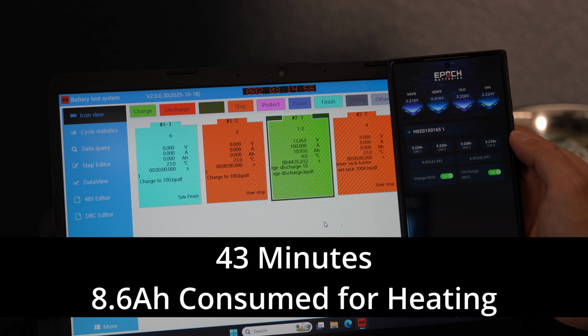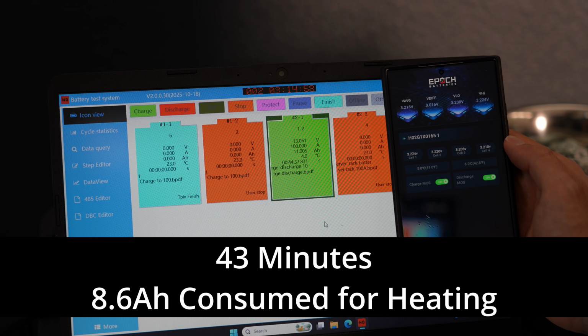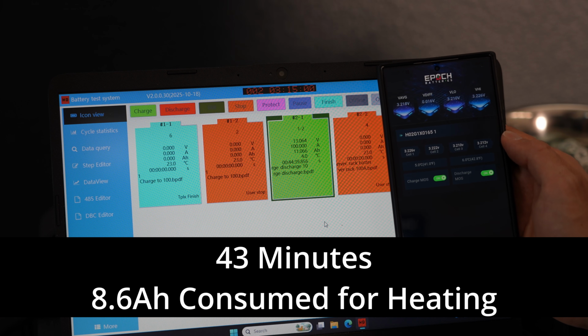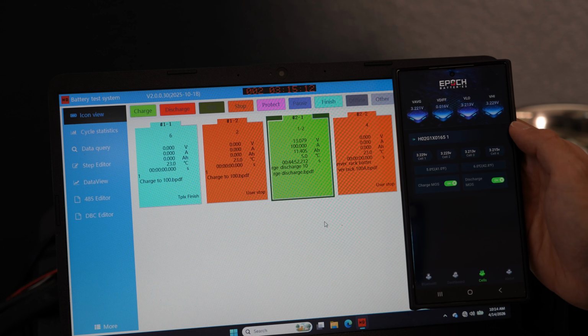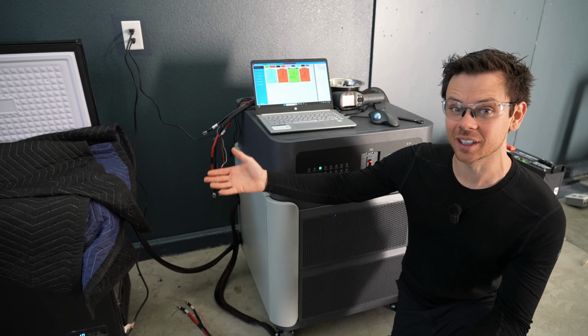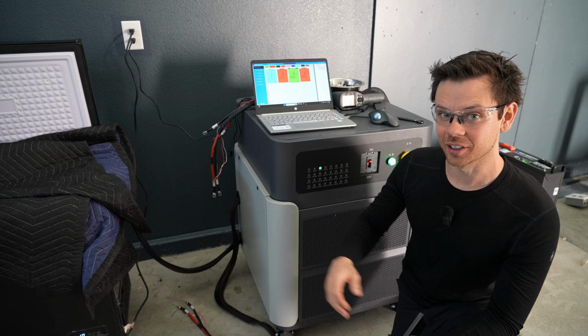So it finally started charging with 100 amps at 43 minutes, and we're at 5 and 6 degrees Celsius for the temperature sensors - pretty conservative. They want to ensure the cells are actually warm. Now the freezer is still running, so let's see what our capacity is with these internal heaters.